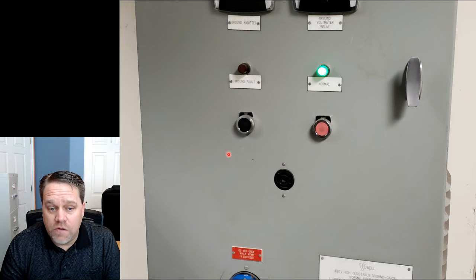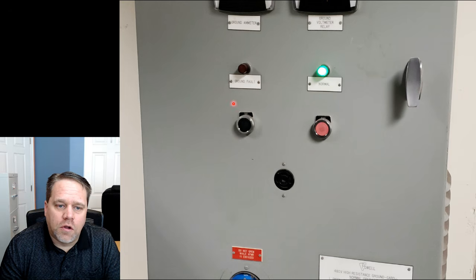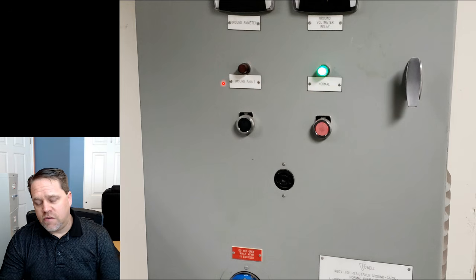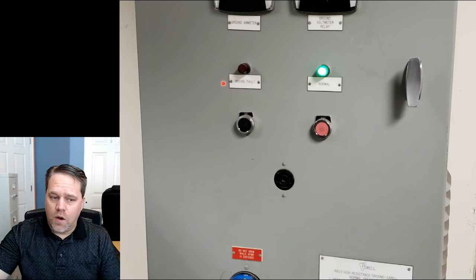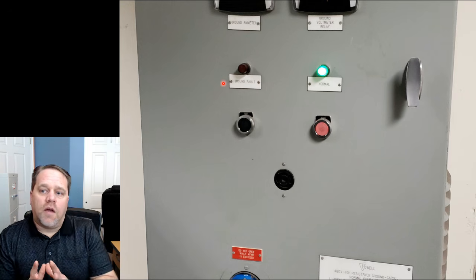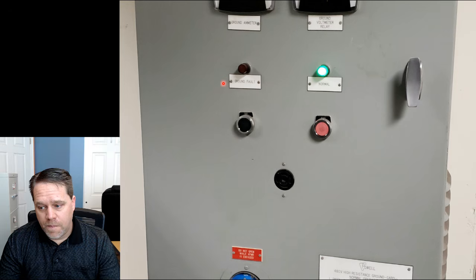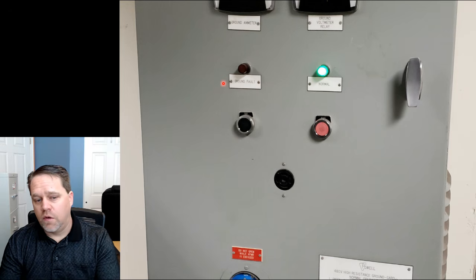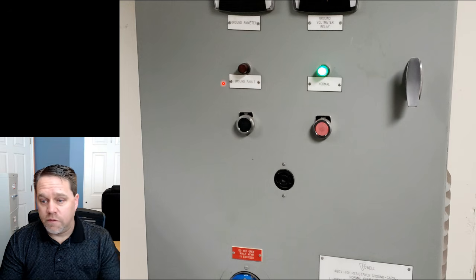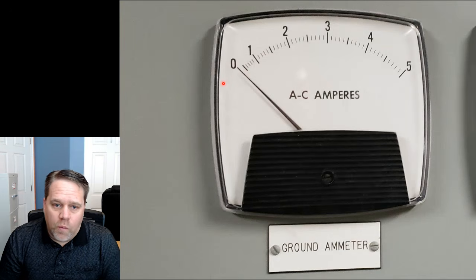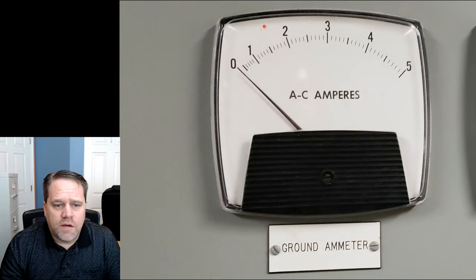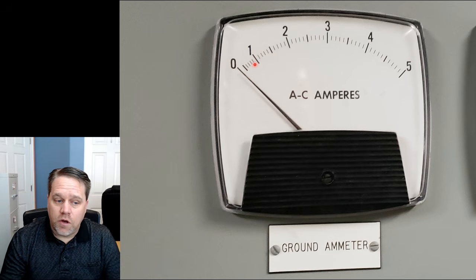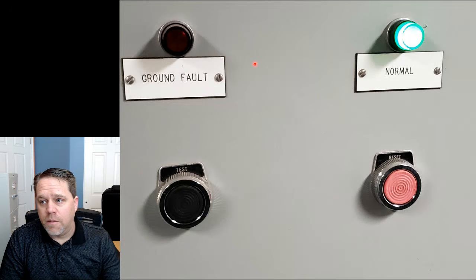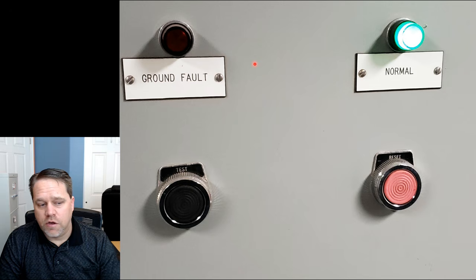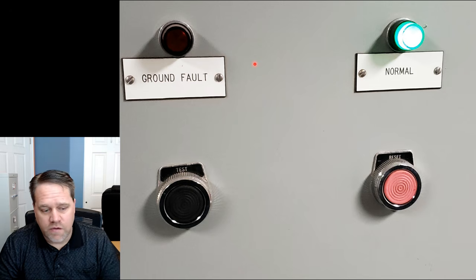So here is the front of that piece of equipment with the cover closed, and you can see that it's in normal condition. If there was a ground fault, this alarm would go off. The breaker wouldn't trip because the resistance is high enough that it puts the current so low that it could never initiate the overcurrent device. My resistance on this resistor is about 277 ohms. So if it's a 277 volt ground fault going through a 277 ohm resistor, then that would be 1 amp of current, right? I equals E over R. So we have this on the front of that piece of equipment, and if this thing moves up to like 1 amp, 1.5 amps, then we know we have a fault. And when a fault happens, instead of the breaker tripping, the alarm goes off. And that allows the electricians to go through and troubleshoot the system and make sure everything stays operational.